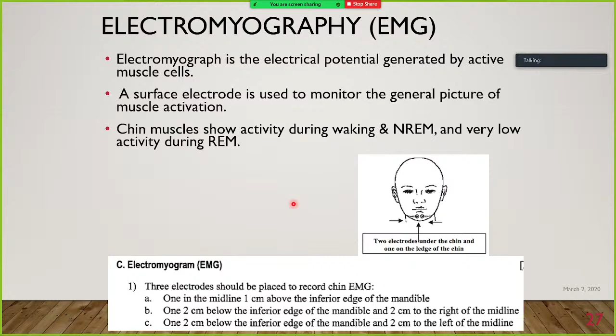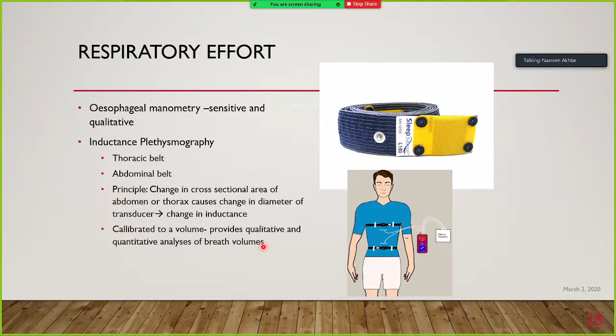All right, so the other thing that is recorded is the respiratory effort. So for this effort, this is the sensor, what it looks like, and it is put around the chest and the abdomen. The most accurate is esophageal manometry, but it is not used routinely. It is not recommended. What is used is the principle of inductance plethysmography. There is a change in the cross-sectional area of the abdomen or thorax, which causes a change in the diameter of the transducer. And because of the change in the diameter of the transducer, there is a change in the inductance. So this is calibrated to a volume, and this provides qualitative and quantitative analysis of breath volume. Ordinarily in polysomnography, the volume is not calibrated, so what we get are actually only the qualitative readings.